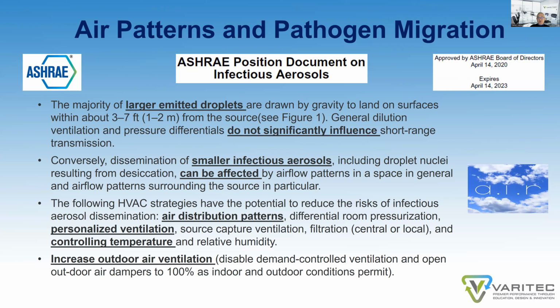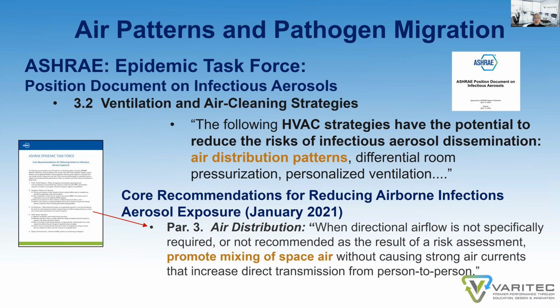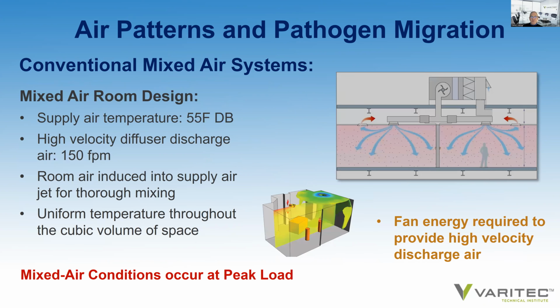Also, the opportunity of looking at increased outdoor ventilation, which I've been speaking to throughout the year. The Epidemic Task Force addresses ways for reducing the risk of infection. And one of those solutions, of course, is air distribution patterns in a space. It goes on to say that regarding air distribution, when directional airflow is not specifically required or not recommended as the result of a risk assessment, promote mixing of space air without causing strong air currents. So ASHRAE recognizes the importance of creating a mixed air environment.